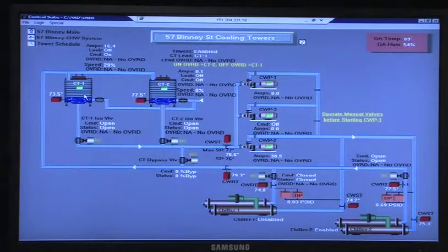This one here is operating at 15 amps on the fans. It's commanded on. It's not overridden. It's a speed. So it's asking for a 29% speed to maintain this temperature, I'm assuming? Yep. This one here is just splashing over, and it's just cascading. This is not operating right now, but it's cascading through for flow, coming to here, and it's mixing, and it's coming to here, and it's getting in at that value. Is that right? Yep. Okay. Everybody get that? I just stepped through the whole thing.